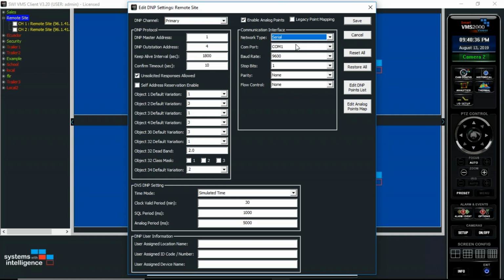The reason why the mapping is interesting is because, different to any other IEDs or even RTUs in the field, we don't have set mapping points. It's completely flexible. We have a total of 256 available points for status points, and you can assign it to any alarm that you want in the way you want.